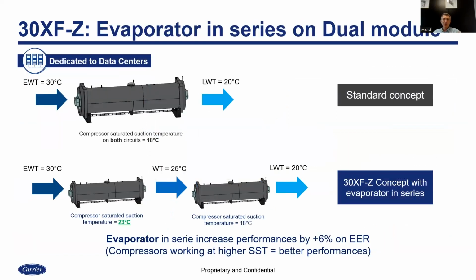Very important elements in our chiller design. I will not make an overview of the entire product lines, but generally speaking, for the larger capacity, if you go above, let's call this 700, 600 kilowatts, we systematically have two modules of the unit side by side. It looks like one machine, but actually it's two independent modules with two independent evaporators. And this is a very important point, because what happens is water enters the first evaporator and then goes in series to the second one, and the final cooling is provided by the second evaporator.